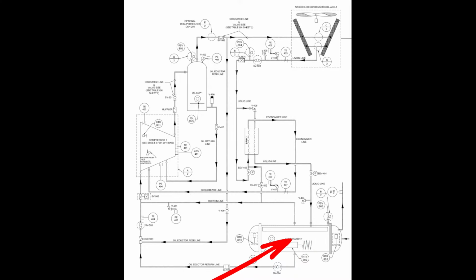Same fundamental style. And when I see the schematic differences between the two, Style A and Style B, it appears to me that the evaporators they're using on the Style B do maintain a higher liquid level than what I was seeing on the Style A machines. Just the way that the piping and the internal baffling layout looks based off of their manuals and documentation, that would be my expectation: you would see slightly higher levels on these evaporators compared to Style A, which we would also see in the sight glass. All right, so these do have a sight glass on them, and that sight glass, I believe, is probably a little bit higher up on the barrel, but we're shooting for the same thing either way. We do still want to maintain about 1/3 to 1/2 glass on these evaporators if we're properly charged and everything's working properly.